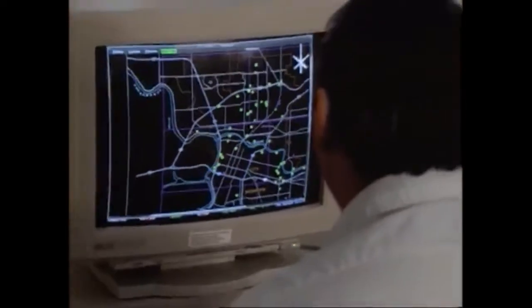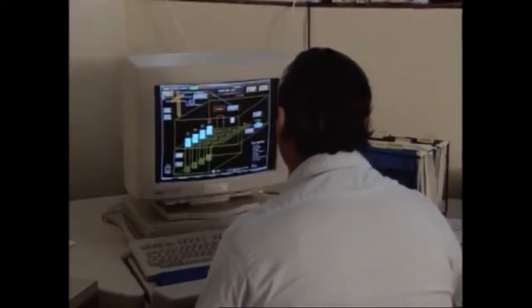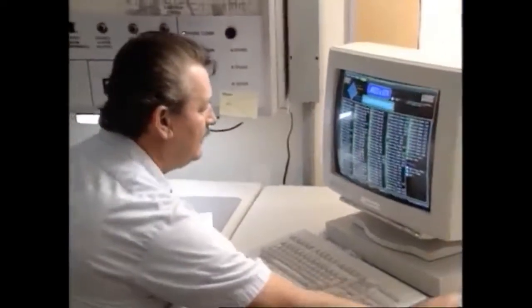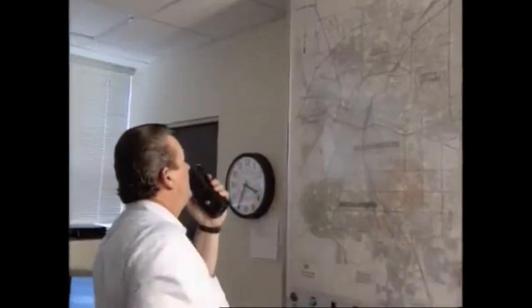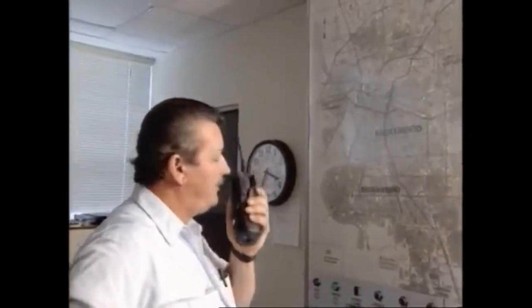Most lift stations constructed today have a telemetry system that monitors for a high water alarm. Usually other items may be sensed and alarmed on the same high water alarm signal. For example, water level in sump pump pit of dry well, power failure, air compressor failure, telemetry failure, pump motor failure, lift pump check valves, inside temperature, and alarms indicating break-in. On a lift station with auxiliary equipment, the following items may be telemetered: water supply pressure, chlorine leaks, low chlorine pressure, high temperature of motors and engines, and standby generator operation.